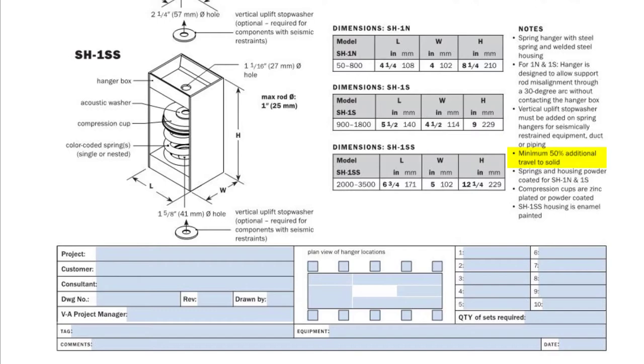So while it would still be safe when solid we don't want to see any springs that are flat or even near flat on a job site because that would mean that either the springs were misselected or misadjusted. Springs in any spring isolator should be close to their design deflection.